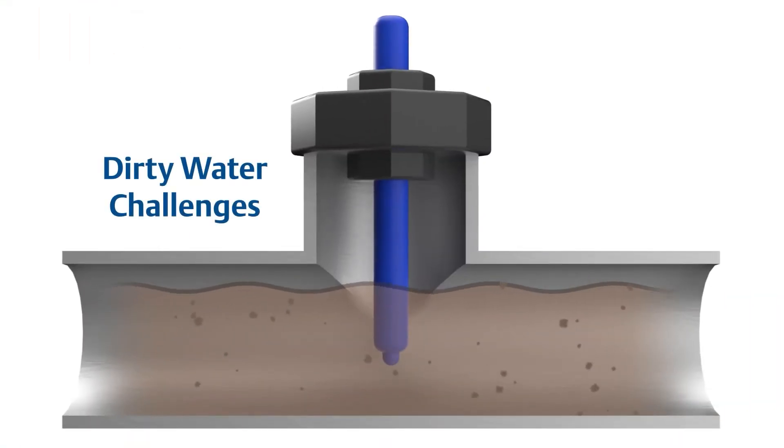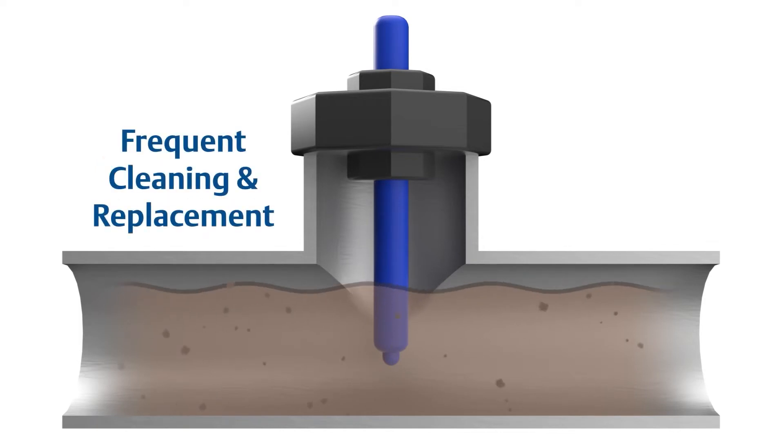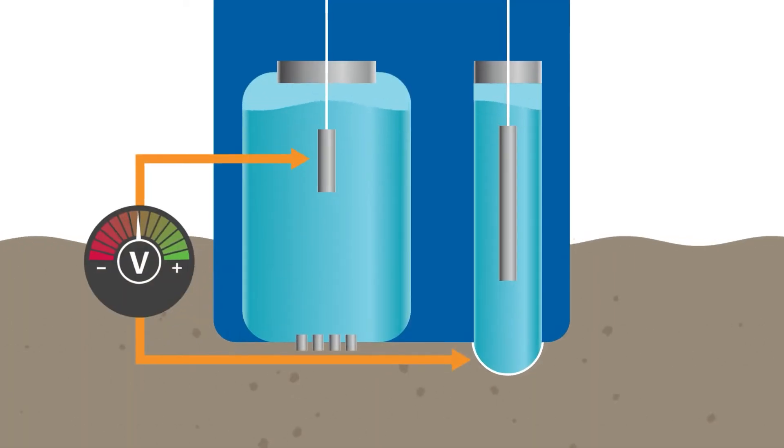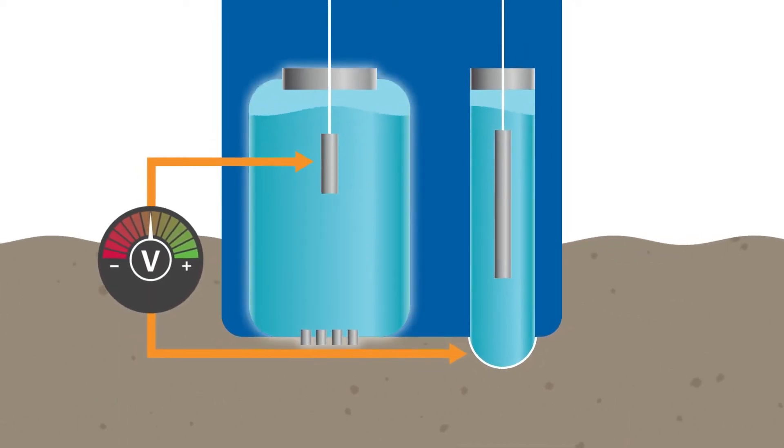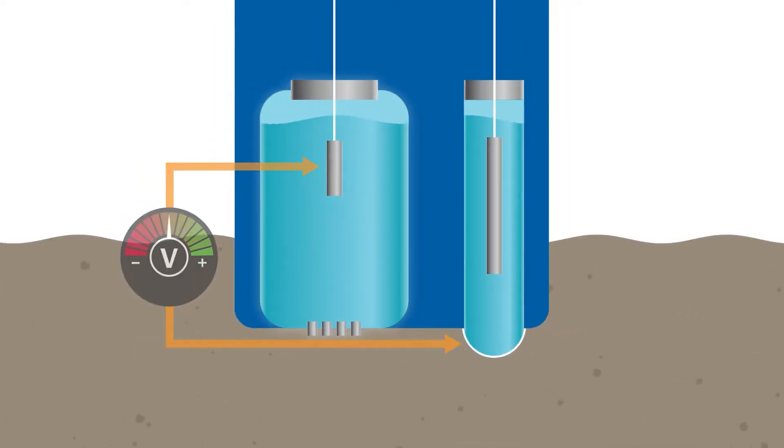In applications with dirty water, pH measurement can be challenging, requiring frequent replacement and cleaning of sensors. Here's why: pH sensors work by measuring the voltage difference between a pH-sensitive measuring electrode and a stable reference electrode.